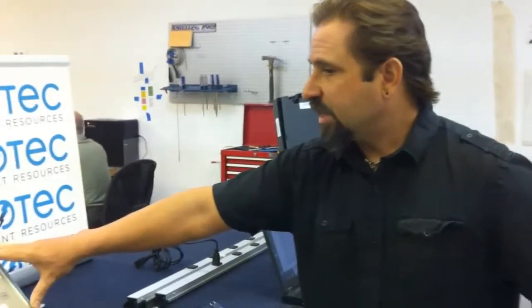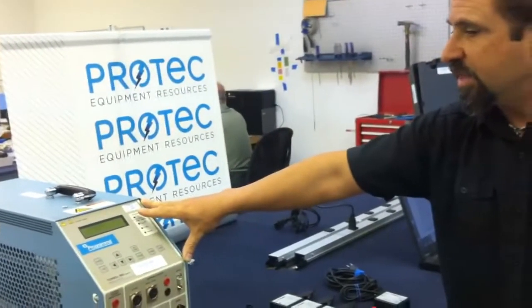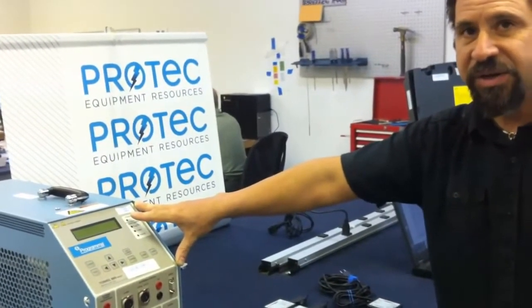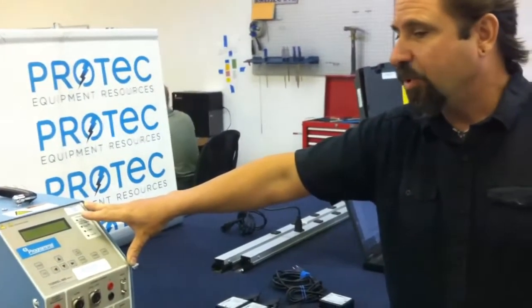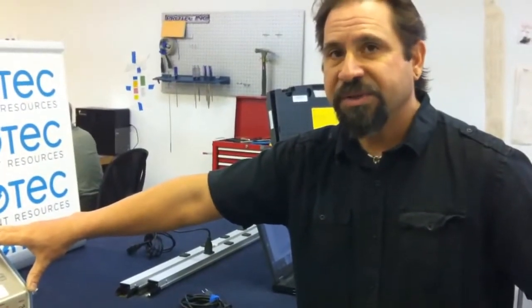The unit is a load bank set for DC discharging of stationary standby batteries. It is capable of connecting onto battery systems from 12 volts up to and including 480 volts. Through a single TORKEL unit, it will allow up to 110 amps of current to discharge through. If you do require to go higher in amperage, simply we would parallel additional load bank units and be able to step up in 110 amp increments.